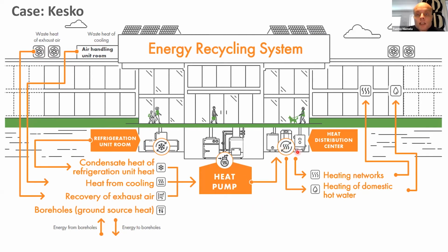We produce heat to a heat distribution center, where it's divided into different heating networks of the property—ventilation heating, space heating, and domestic hot water heating. With this system, even without boreholes, we can achieve as high as 95% coverage of heating energy, so the additional heating energy requirement is quite low.